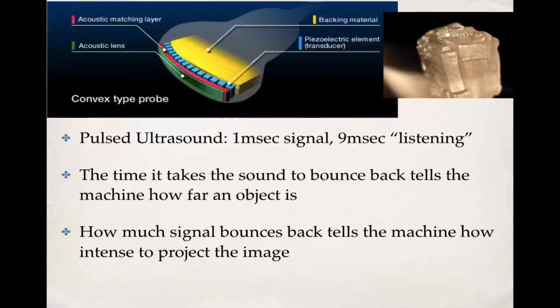It shows you how the crystals are sort of marched out in line at the end of the transducer, and those are again vibrated with an electrical current and send a mechanical wave through the patient. And it's worthwhile to note that the transducer functions in a pulsatile way where it sends a signal out for about 1 millisecond, and then it listens, or it kind of absorbs those sound waves back in order to put them up on the image for you for another 9 milliseconds. So only shooting out waves for about 10% of the time. The vast majority of the time it's listening or kind of recording those sound waves coming back to it.